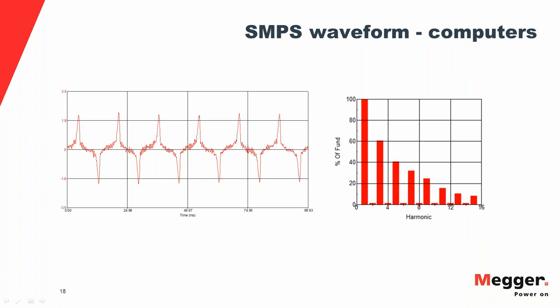Looking at a real waveform from a computer, there is strong similarity to the simulation: sharp current pulses caused by the capacitor in the switch mode power supply. The harmonic spectrum on the right shows the magnitude of each harmonic order relative to the fundamental (at 100%). The spectrum shows mainly odd harmonics — third, fifth, seventh, ninth, eleventh — with magnitude decreasing as order increases. Though the current drawn by one computer peaks at about two amps, a building with 50 to 100 computers would have significant zero sequence harmonic current in the transformer neutral.